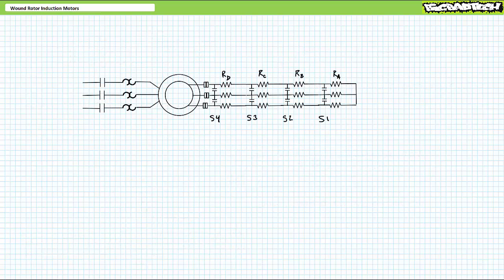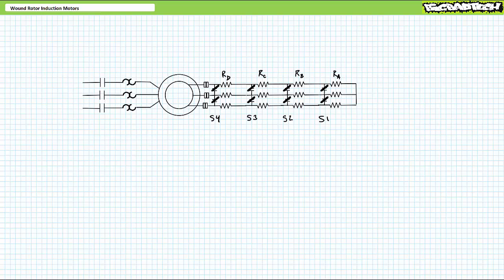Rotor resistance needn't be an all-or-nothing implementation. Consider a bank of resistors and shunt contactors. When all shunt contactors are open, resistors A, B, C, and D are placed in series with the rotor, giving the rotor maximum resistance. When shunt contactor 2 closes, only resistors C and D are placed in series with the rotor, and thus the rotor experiences less resistance, and so on. Staged closures of shunt contactors 1, 2, 3, then 4 essentially allow a more gradual transition from high to medium to low to no resistance in the rotor circuit. You might use this type of staged secondary resistor reduced voltage starter for a heavy load that takes some time to bring up to speed or decelerate. It's important to realize that resistors employed in these types of starters aren't ordinarily intended for continuous operation and should be switched out in time before they're damaged.